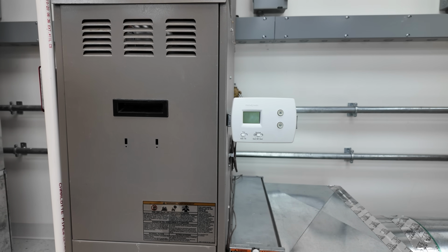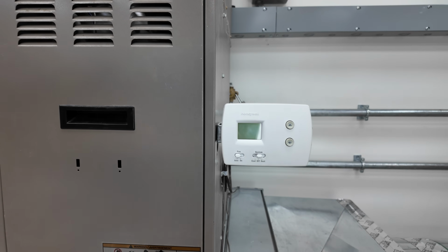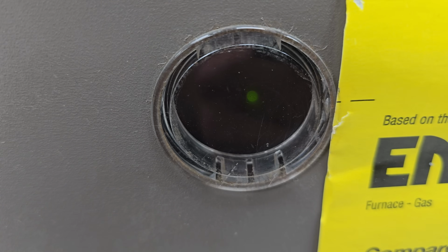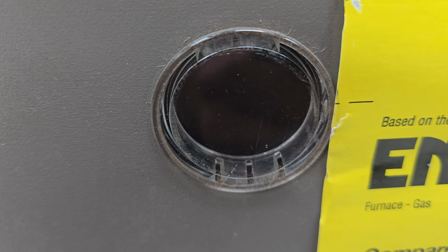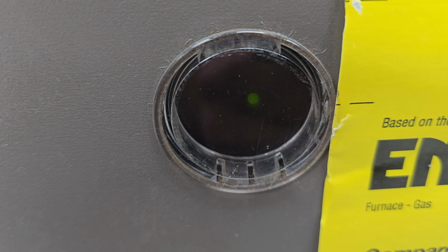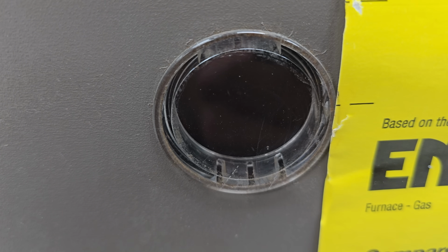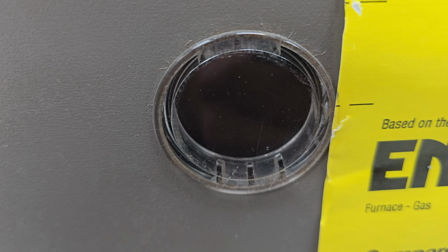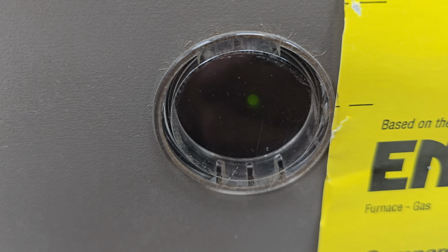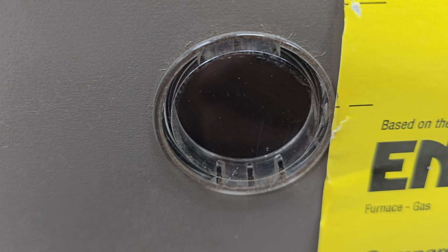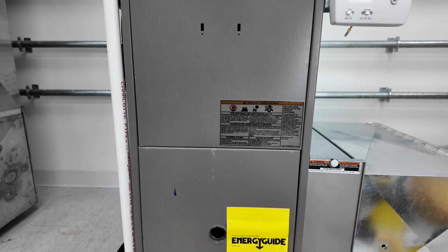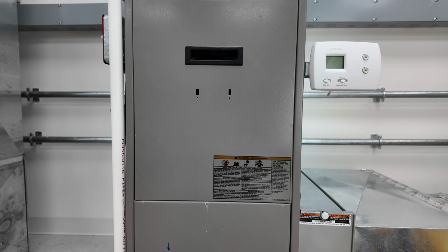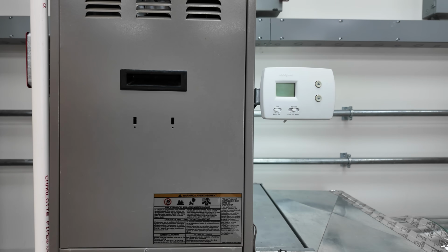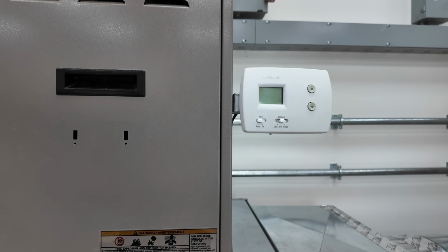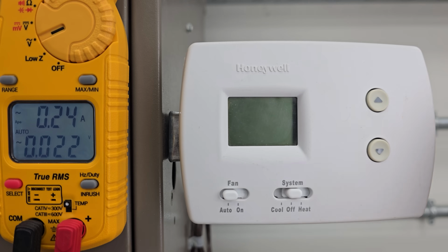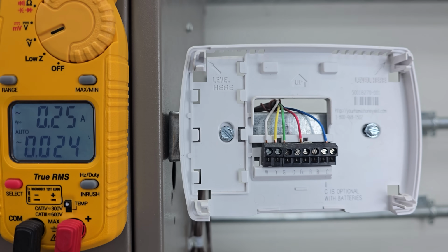So let's start our diagnosis again, and in this case you see that our thermostat once again is blank, and we want to move down to the sight glass as the next step, and we want to see if we see the status code light. In this case you see it's blinking very slowly like normal, but we don't have power to the thermostat. So we know we have 120 volts, we know we have 24 volts, and so we can start our diagnosis right over here at the thermostat subbase. So we need to remove this front cover.